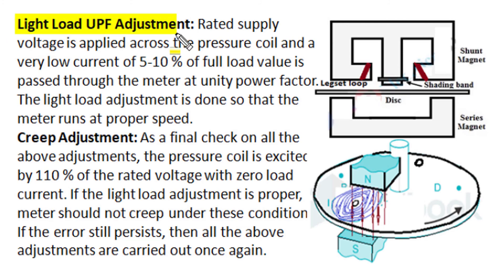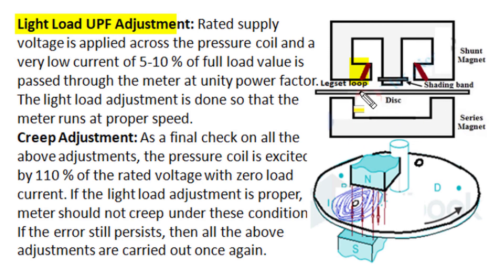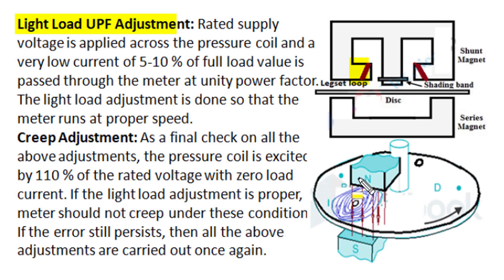After unity power factor adjustment by brake magnet and 0.5 lagging power factor adjustment by the shading band, light load unity power factor adjustment is done once again. Rated voltage is given to the shunt magnet voltage coil, and a light load of 5 to 10 percent of full rated load is passed through the current coil at unity power factor. The lag set loops are adjusted again so that the meter runs with required speed and desirable accuracy. Finally, after all adjustments, the creep condition is checked by exciting the pressure coil at 110 percent of rated voltage with zero current in the current coil.